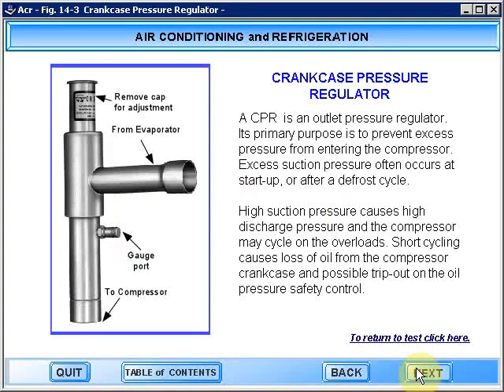A crankcase pressure regulator is an outlet pressure regulator. Its primary purpose is to prevent excess pressure from entering the compressor. Excess suction pressure often occurs at startup or after a defrost cycle. High suction pressure causes high discharge pressure, and the compressor may cycle on the overloads. Short cycling causes loss of oil from the compressor crankcase and possible trip out on the oil pressure safety control.